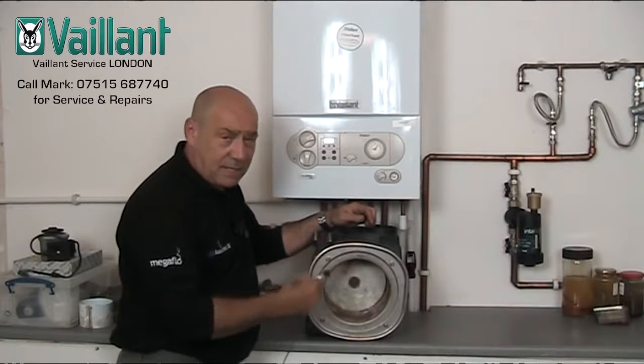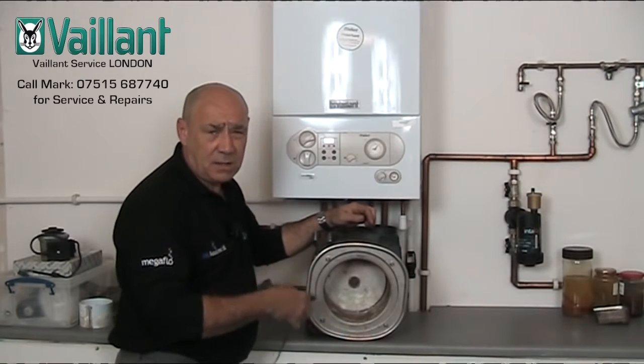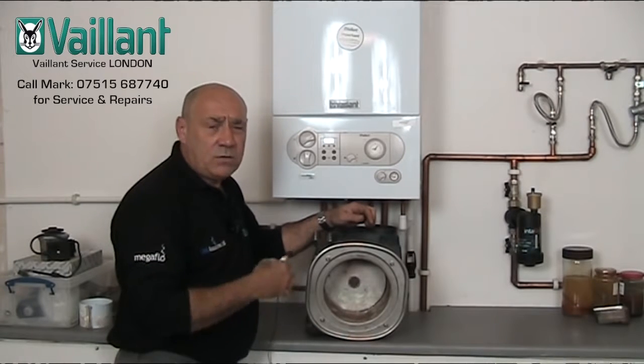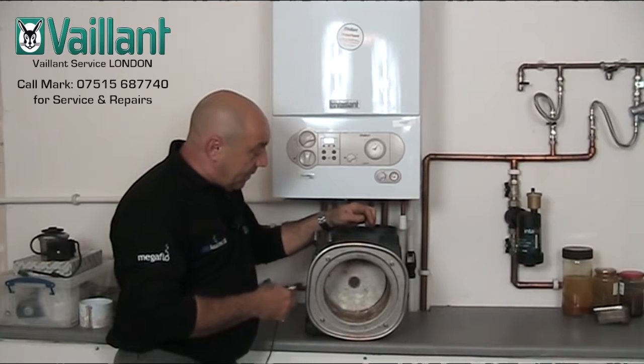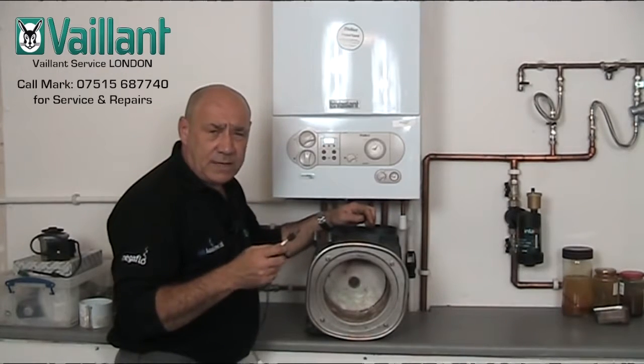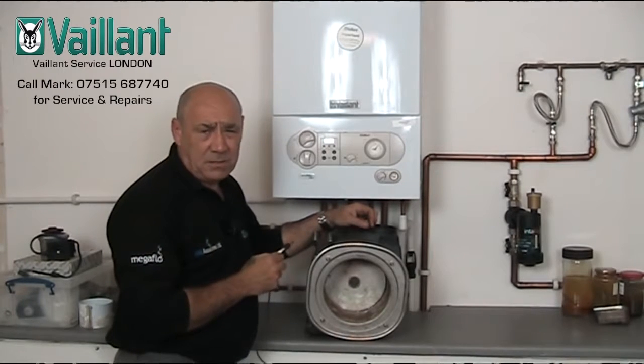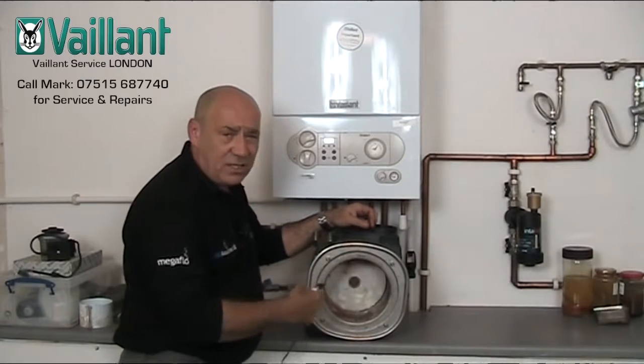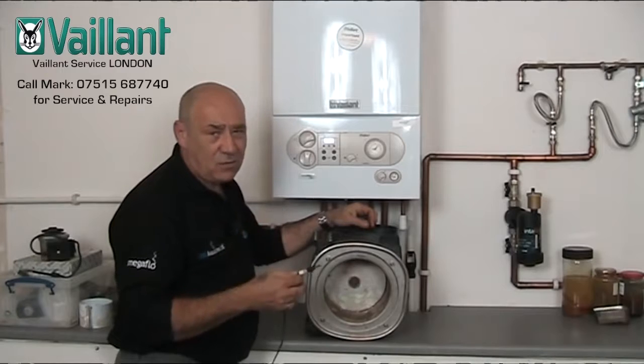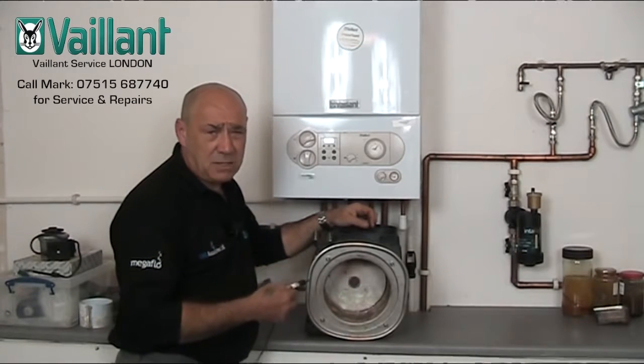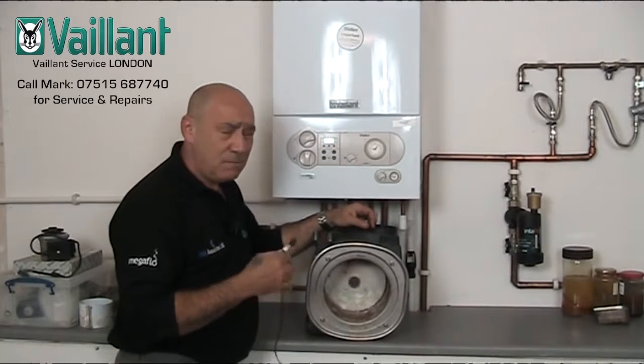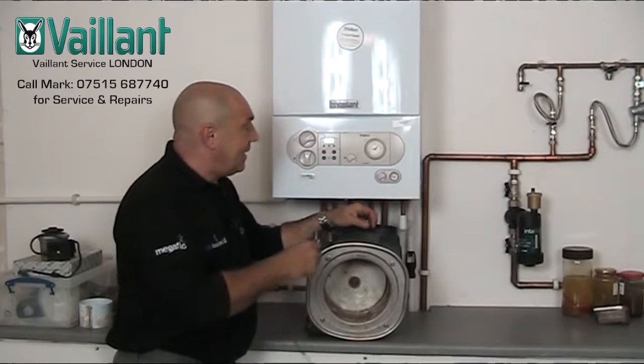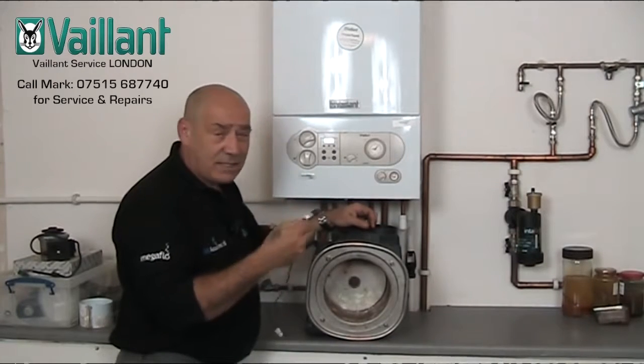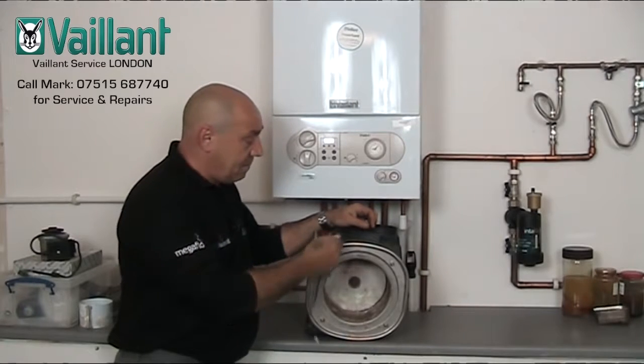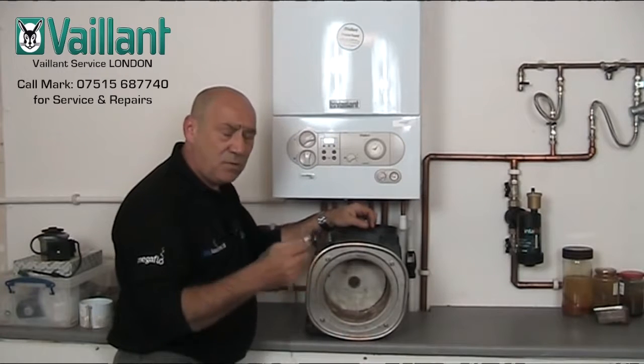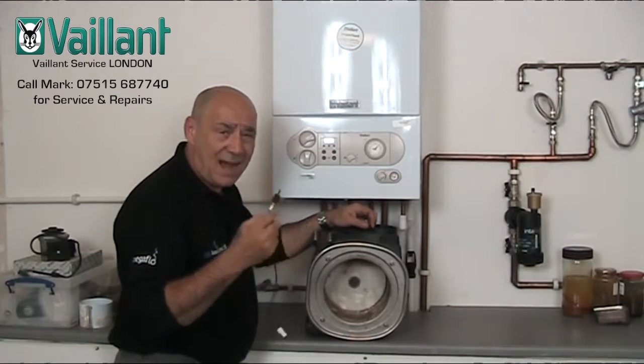Now, how do we prevent this happening? Well, generally speaking, this only happens if the heat exchanger's not got enough water in it to cool it down or keep it at a low temperature. And this normally happens when you turn the boiler on. So, what do you do? Well, Vaillant have already pre-thought this out very cleverly, and what they've done is they've built in a test program into the boiler to ensure that the boiler doesn't come on until the heat exchanger is completely full up with water. Now, it is a critical test program, and every time you work on the boiler or empty the boiler, you must run the P0 test program before you fire the boiler up. What that does is it purges the whole boiler and all the system and the radiators of air, and makes sure everything's full up with water before it comes on and heats up this heat exchanger, therefore preventing this overheating and blowing and then costing you hundreds of pounds.